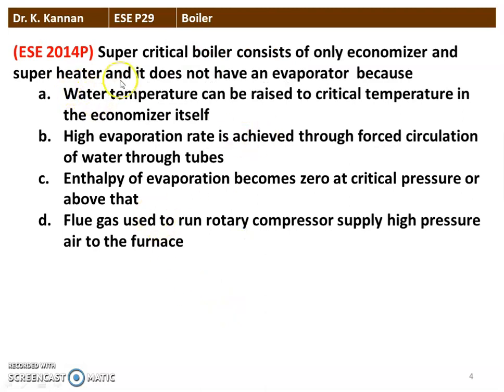Next question again from the 2014 question paper: a supercritical boiler consists of only economizer and the superheater and does not have an evaporator. Four reasons are given: water temperature can be raised to critical temperature in the economizer itself; high evaporation rate is achieved through forced circulation of water through the tube; enthalpy of evaporation becomes zero at critical pressure or above; flue gases used to run the rotary compressor supply high pressure air to the furnace. The correct option is that enthalpy of evaporation becomes zero at critical pressure or above. Since the supercritical boiler operates above critical pressure (above 230 bar), enthalpy of evaporation is zero, so the evaporator is not required — it directly heats water and converts it into superheated steam in the superheater.